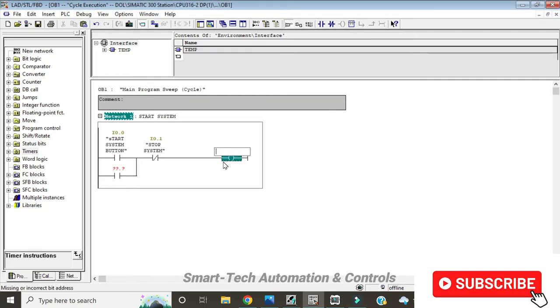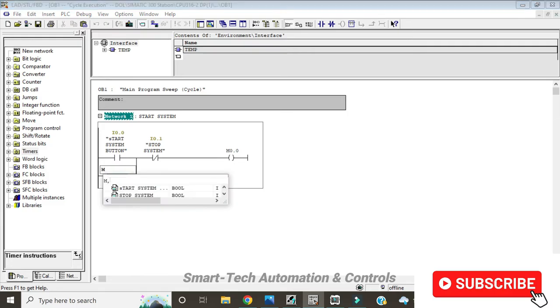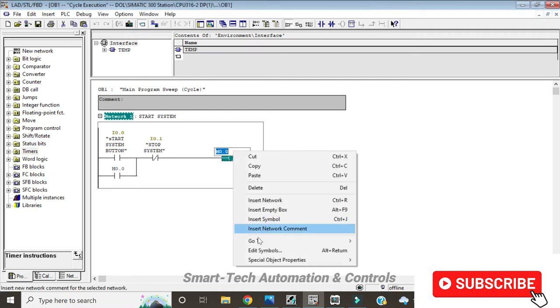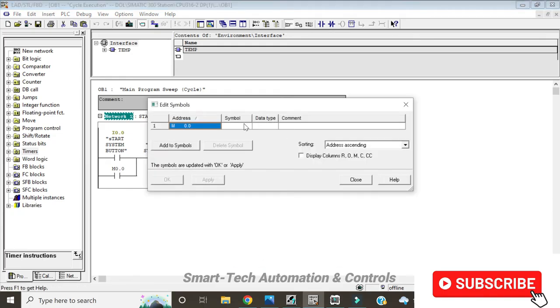For our coil, this one will be a memory, so we call it M0.0. And for the address of this normally open contact on the hold on circuit, it will be the same address as this memory. And so it will be M0.0. We can give this a symbol and call it start memory.